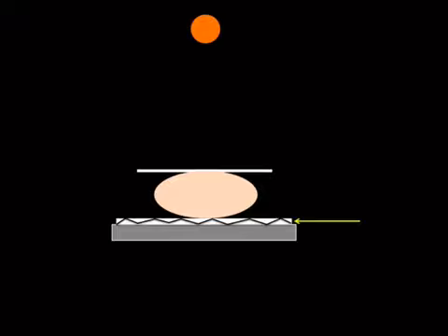Now, another thing that happens is that you're typically using a grid. Since the breast is placed in compression and you're using a lower kVp, both of which intrinsically reduce your scatter, a smaller grid can be used.